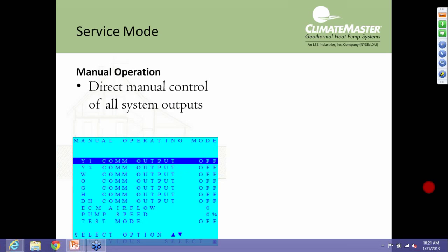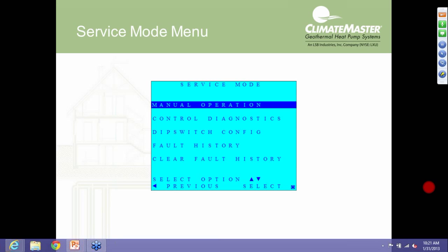All right, first thing, there we go. Under service mode is manual operation, control diagnostics, dip switch configuration, fault history, and clear fault history. Under manual operation, just what it says, we can manually run the unit. Control diagnostics, we can look at what's going on in the unit. We can look at all our temperatures from all our thermistors. We can look at control voltage, flow, airflow, and water flow. We'll get to that in a moment.